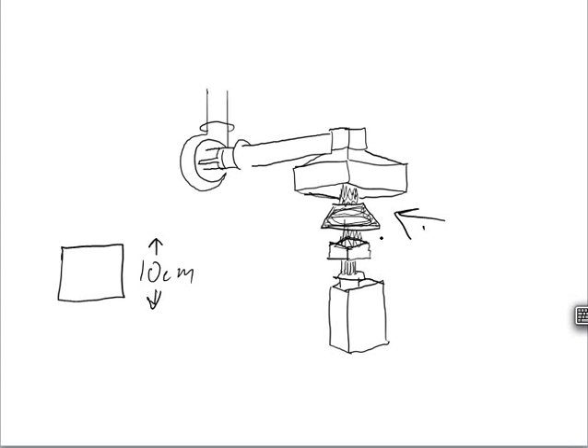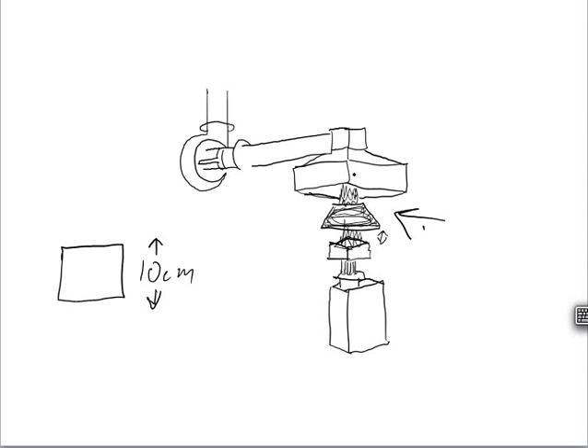And then you can either let it auto-ignite, or you can use a spark igniter to ignite it. It's held 1 inch, 25 millimeters below the bottom of the cone, and the cone shape is supposed to generate a nearly uniform incident heat flux across the surface, so it's a good way to test. This particular apparatus is described in ASTM 1354 if you want a standard to go with it.